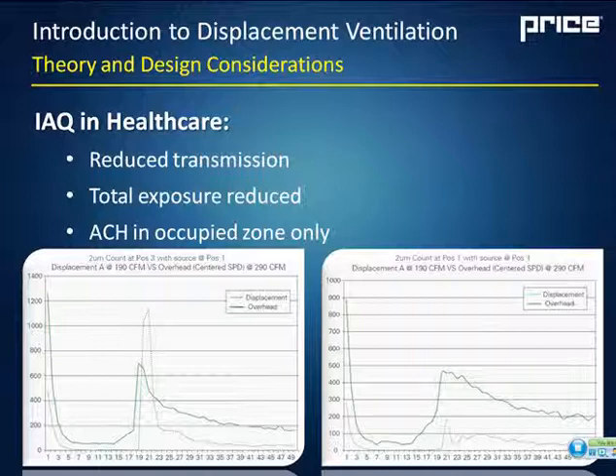Now, another thing that we're seeing as a distinct advantage for displacement ventilation in healthcare is that the AIA and the FGI Facility Guidelines Institute is now recognizing displacement ventilation as far as the air changes in the occupied zone only. So if you're looking at a patient room or a waiting room area, and you have to have your 4 or your 6 air changes per hour, with a displacement system, they're now allowing you to do that calculation with the volume of the occupied zone, which is only the 6-foot height, instead of the 9 or 10-foot ceiling height, or whatever it may be, with a standard mix system. So the discount there with air delivery, the volume of air that you have to deliver, is quite significant.